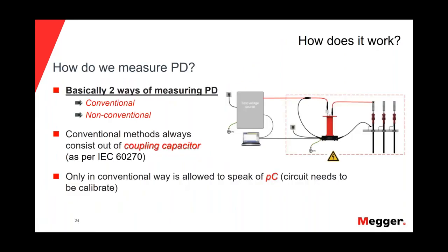So how does partial discharge work? As I mentioned, we have two ways to measure partial discharge, the conventional way and the non-conventional way. In the conventional way, we need to connect in the circuit between the power source and the cable under test a coupling capacitor. So we need to de-energize the cable in order to connect the coupling capacitor and the power source.